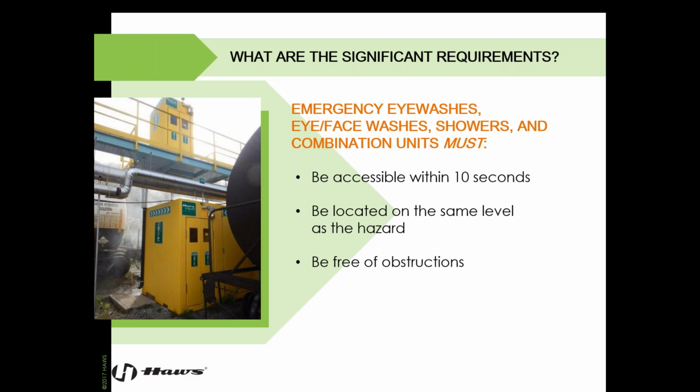location, installation locations. The equipment needs to be located on the same level as the hazard. So if you have an employee that's on the second floor, the unit needs to be on the second floor if the hazard is there as well. It needs to be where the worker is at. No stairs, no flights, no elevation differences.